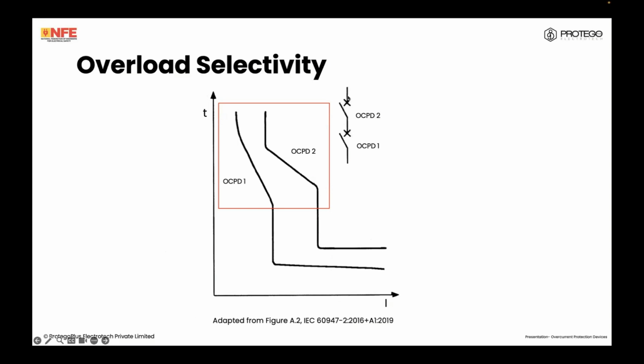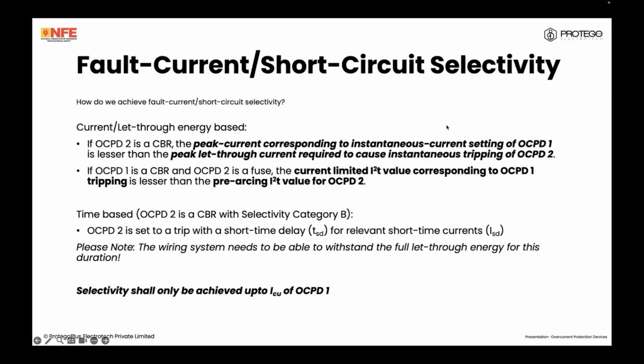You can ignore the fact that these are both circuit breakers, by the way. This could be a fuse and a circuit breaker, or a circuit breaker and a fuse, or a fuse and a fuse, for that matter. Remember, like I said, OCPD1 is the one closest to the fault. OCPD2 is the one upstream of this OCPD1. This is adapted, by the way, from figure A2 of IEC 60947 Part 2, 2016 plus Amendment 1 in 2019.